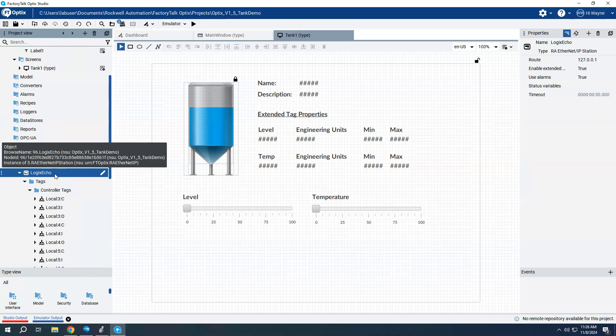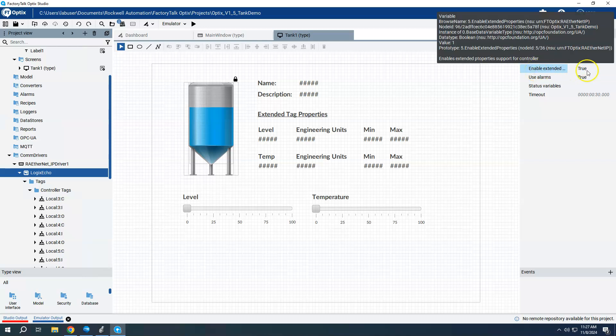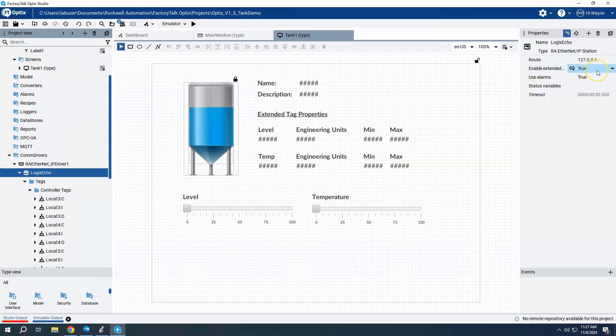I have a COM driver created, also have the device of type RA Ethernet and then I have a new station, I guess is the proper term. If I click on the station, which is the Logix Echo, over here in the properties window on the right, I have basically two things that need to be turned on as true to do some of the things I want to show. So first to use the extended tag properties, I need to make sure this is true. Initially, when you created the station, it actually was set as false. And then if I want to use the tag-based alarms, I would also need to turn that on to true. So again, on a follow-up video, I'll show the alarms, but I already have it turned on here. And then you would do your tag import.